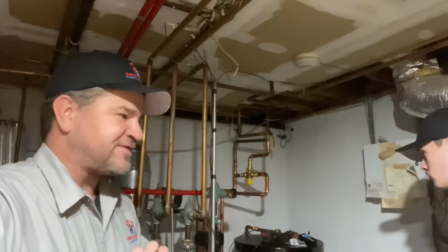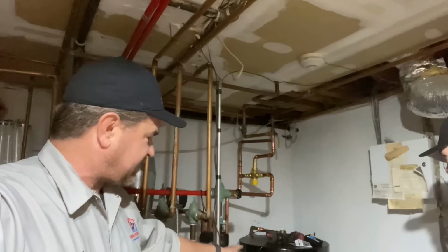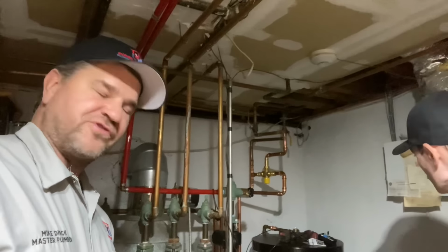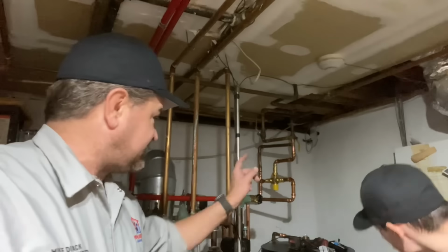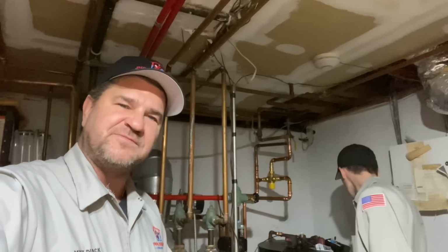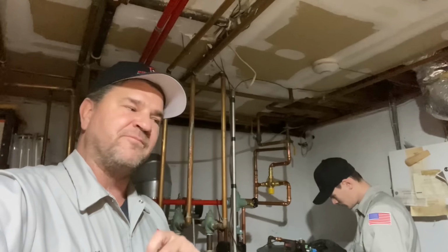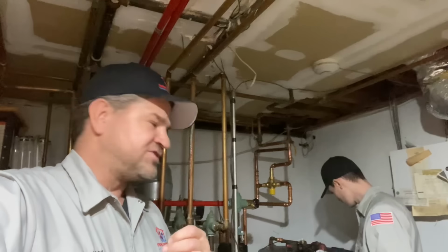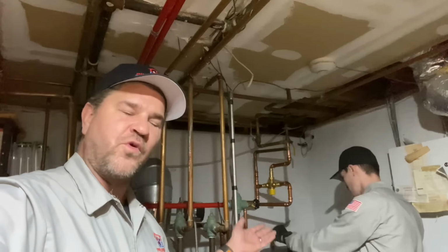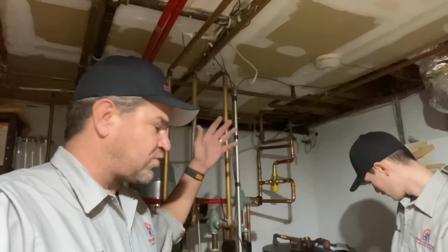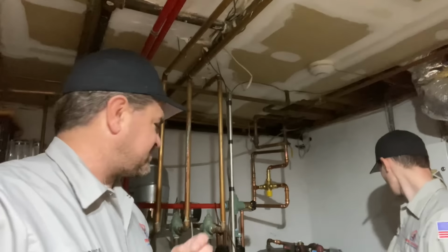I don't know what the exact specifications of the numbers are, but if I crank up that aquastat to 180 degrees, which matches the high temperature limit of the boiler, and when I install a thermostatic mixing valve, I'm going to maximize the gallons per hour of 120 degree water that this tank can produce for this household. So let's say I only set it for 120 degrees. Obviously, we're going to run out of water much quicker. If the tank is 180 and my thermostatic mixing valve is mixing that water down to 120, tempering it down to a lower temperature, to maximize the gallon output, that's what we do.